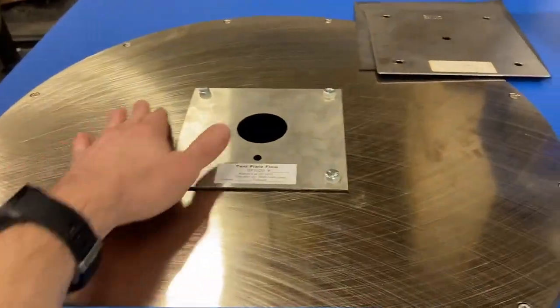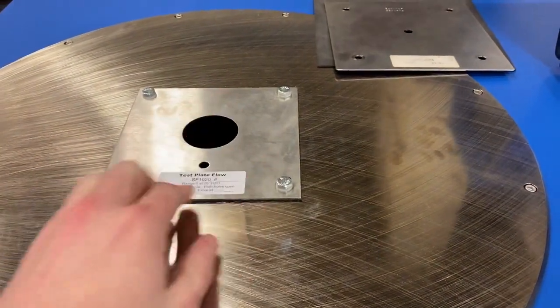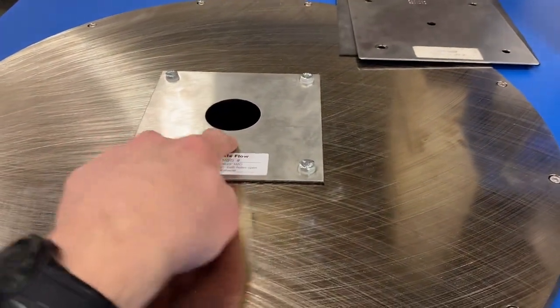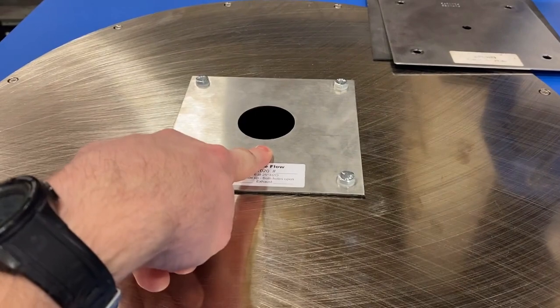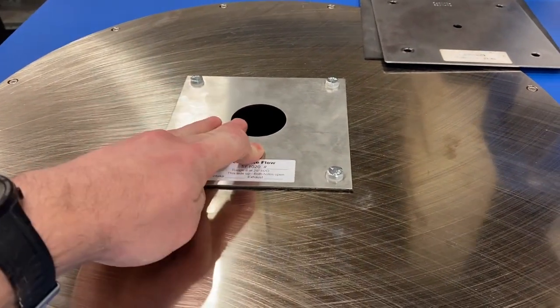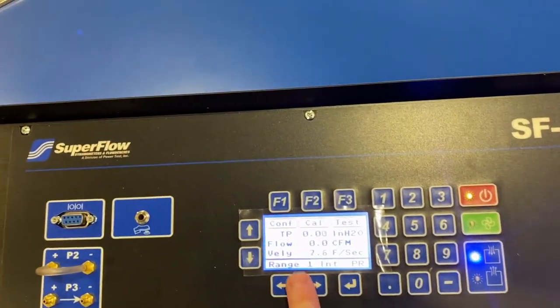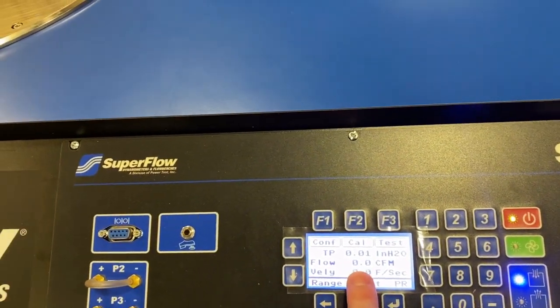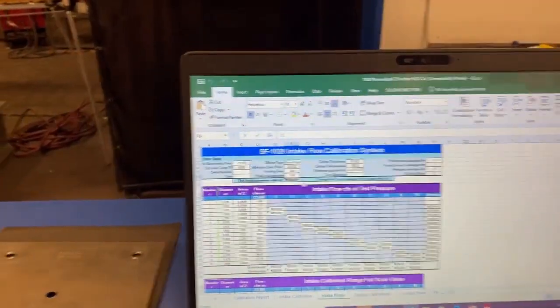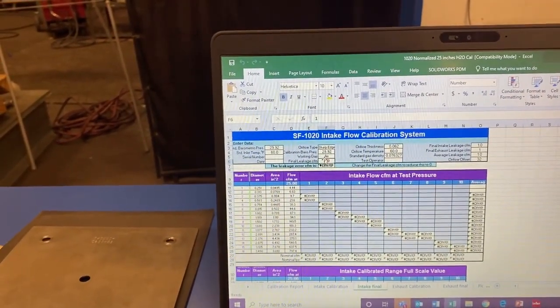At that point, we would use the rubber stopper to plug up the larger hole, and just our finger. Wet your finger if you need to, and make sure this is sealed. And with the rubber stopper and our finger plugging these holes, we would be able to give a good leakage value under flow. Whatever this flow says after it stabilizes, you would then come in here and put that value in this field right here.